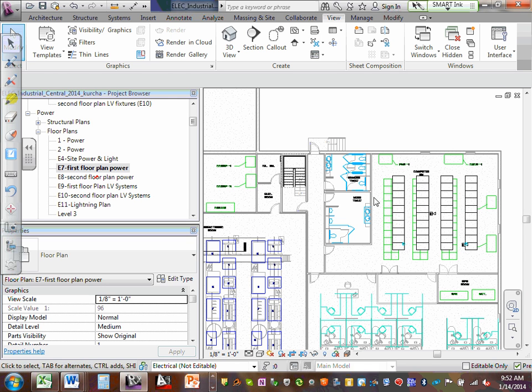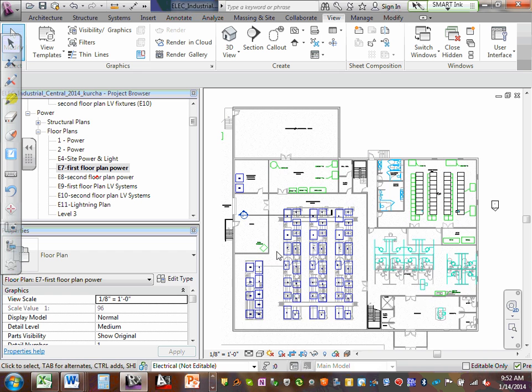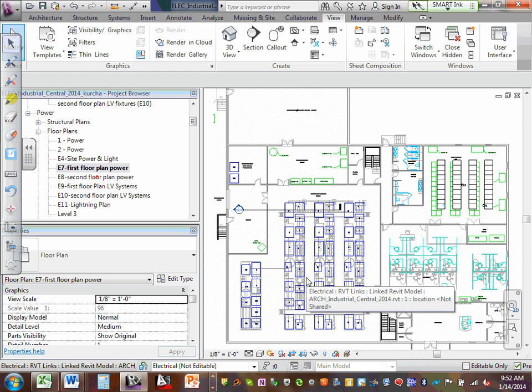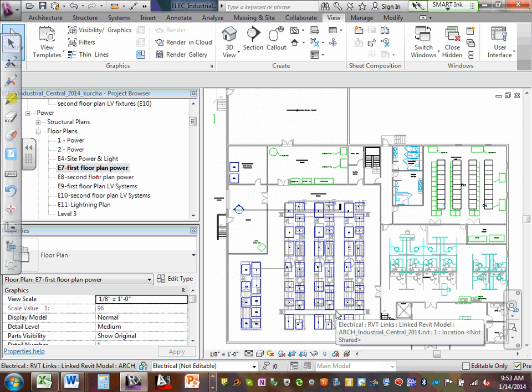Okay, great. So I don't know where you want to start. Well, let's start with manufacturing, and I like the idea since you have a high ceiling, 21 foot. It is difficult to place area type smoke detectors, so photoelectric beam or photo beam smoke detection is a great application for this device in this room. The reason is you've got a 21 foot high ceiling, and you're about 80 foot by 80 foot, almost.